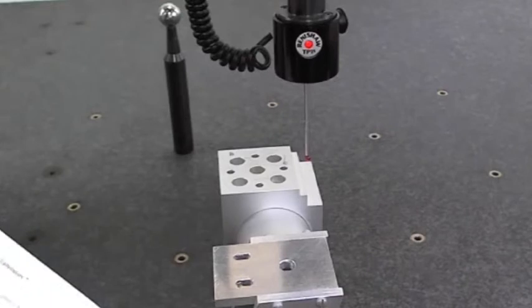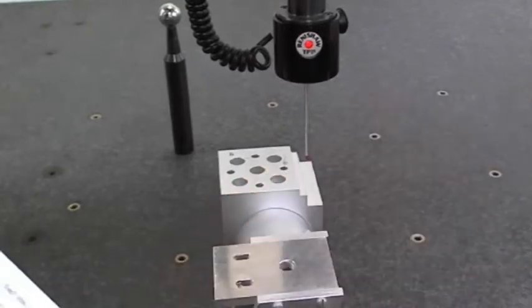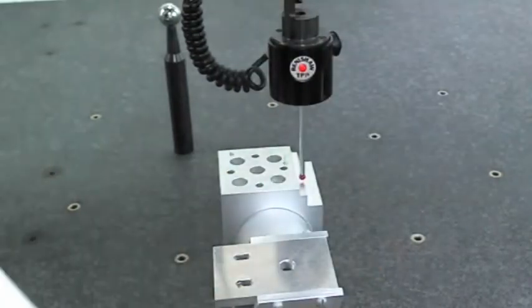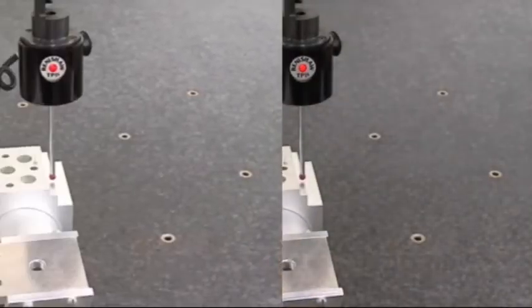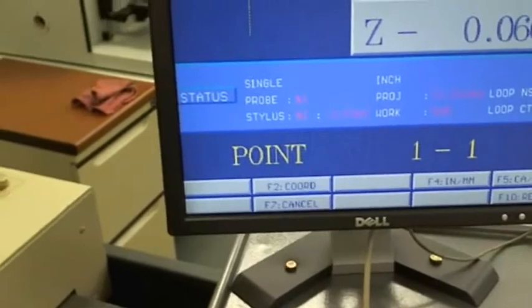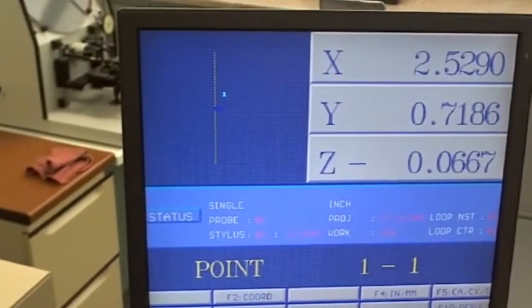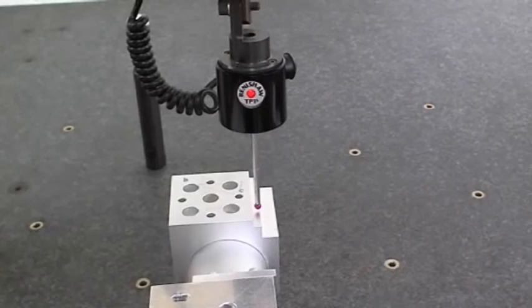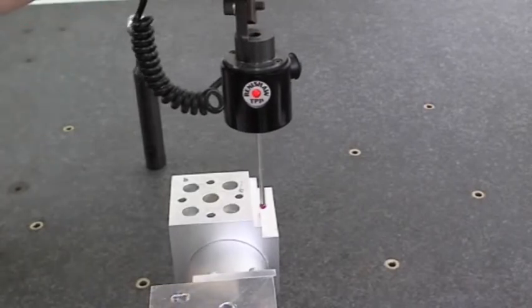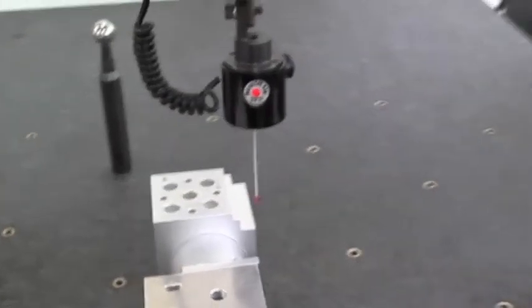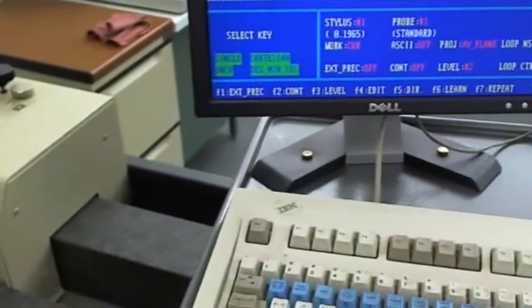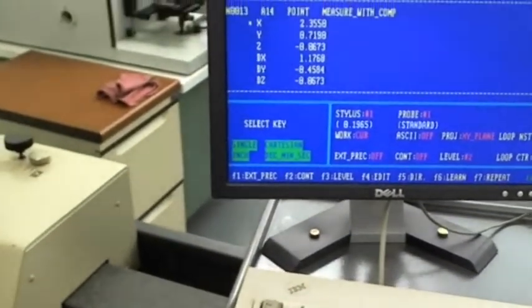Now, this is a little bit more tricky than it looks. I've turned off my control box, and I'm positioning the probe along this area here. Now I'm going to press this button to measure the line, the first step for the C dimension. I've already pressed the left button, and you'll notice that it is flashing against that surface. Turn on the control box, hit the point. Next, you'll notice that X is 2.355. That is the dimension that we measured.